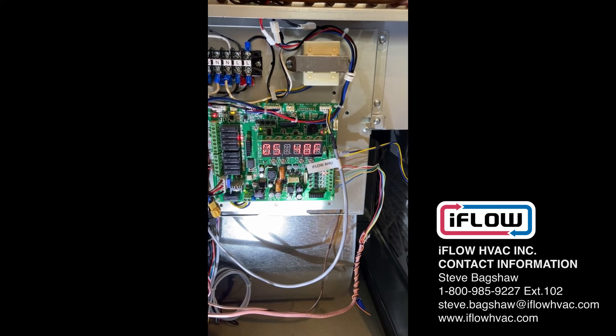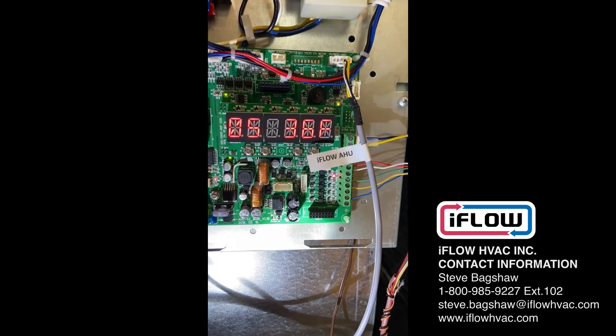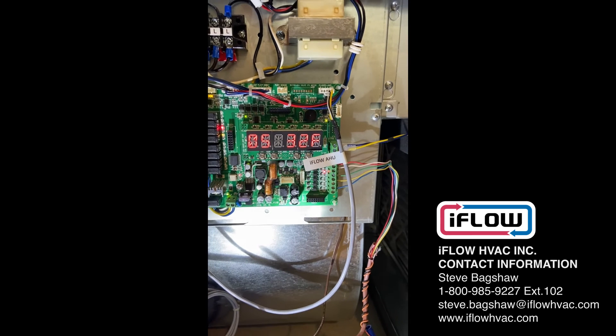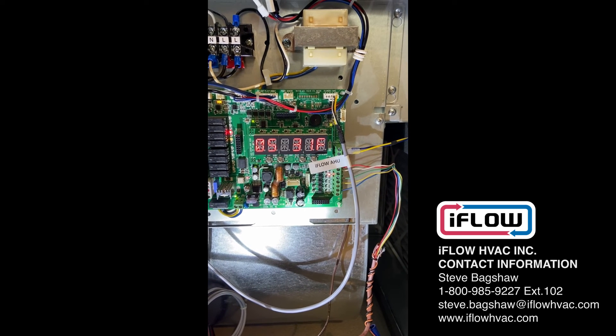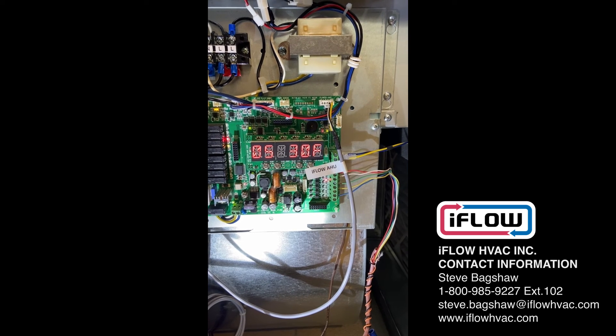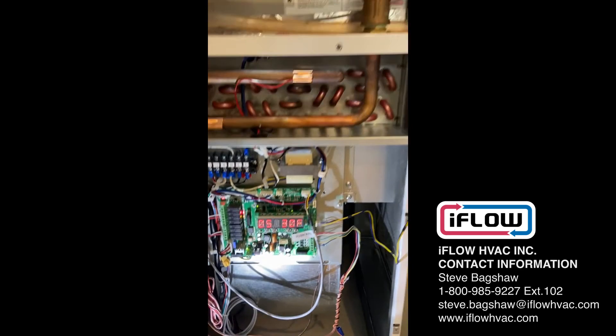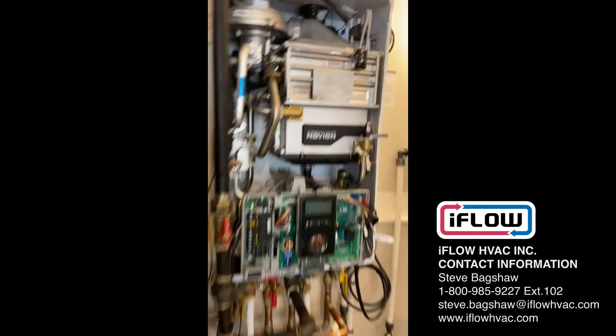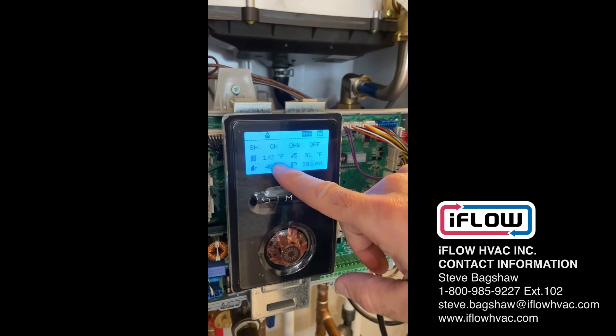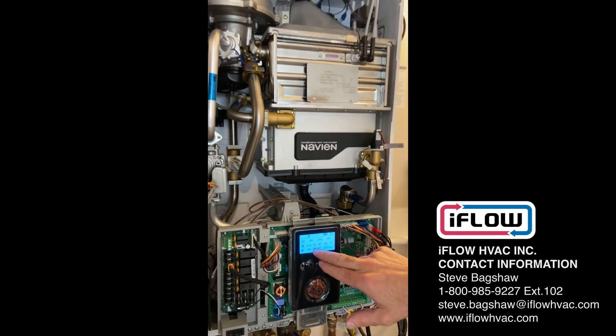Let's bring this down a little colder — down to around 30 degrees. So now we're at 30 degrees outdoor temperature simulated. What do we have on the Navien boiler? 141, 142. Again, it's automatically calibrating between the two to deliver only the BTUs that we need.